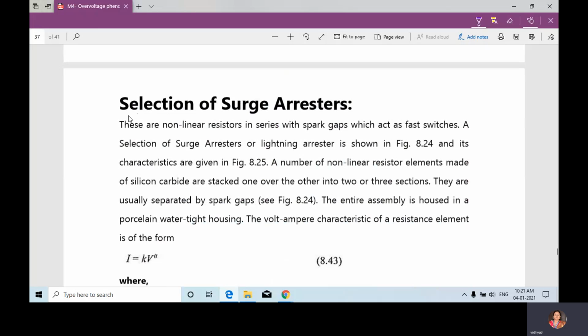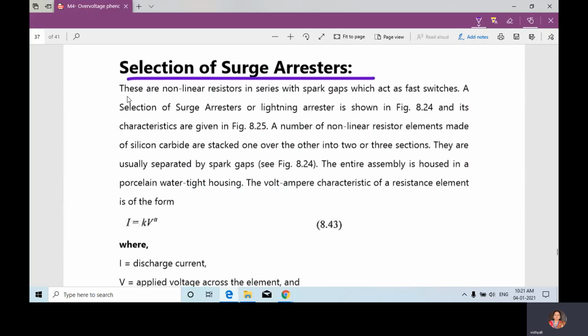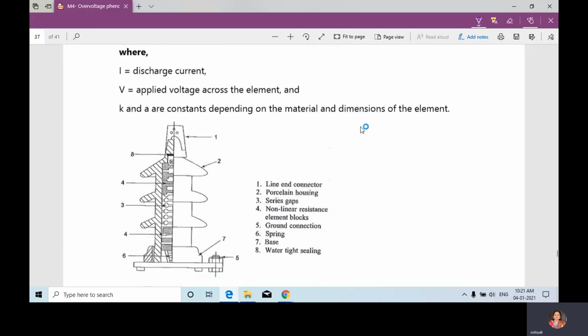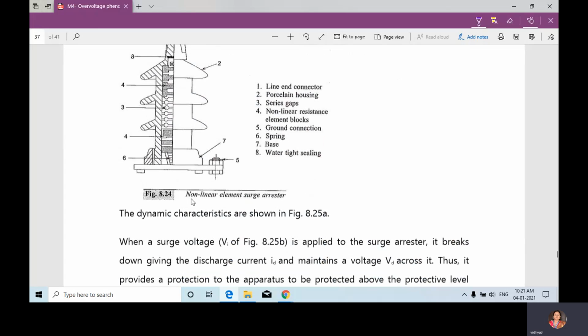Next is the selection of surge arrestor. How do we select the surge arrestor? There are nonlinear resistors in series with the spark gap, which acts as a fast switch. This is the selection of a surge arrestor or lightning arrestor. You can see this figure. Okay, this is a figure of a non-linear element surge arrestor.